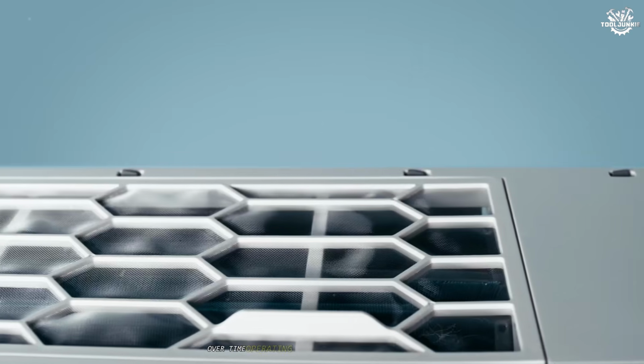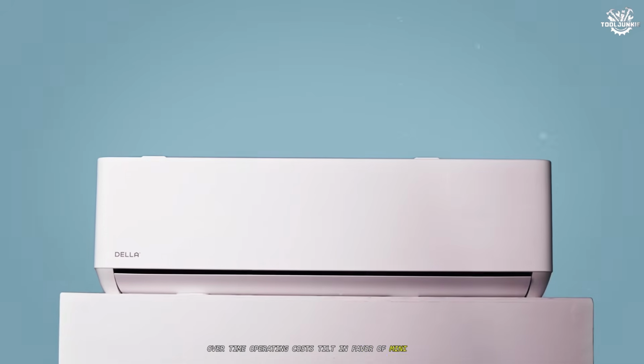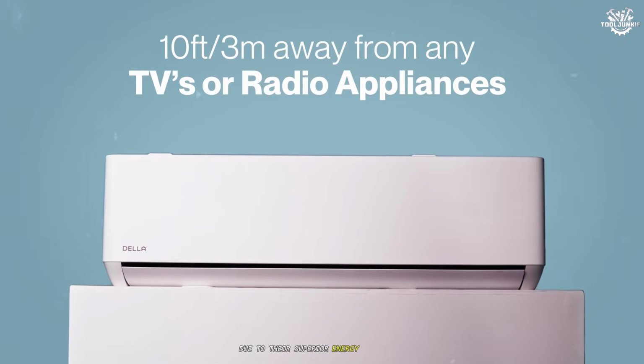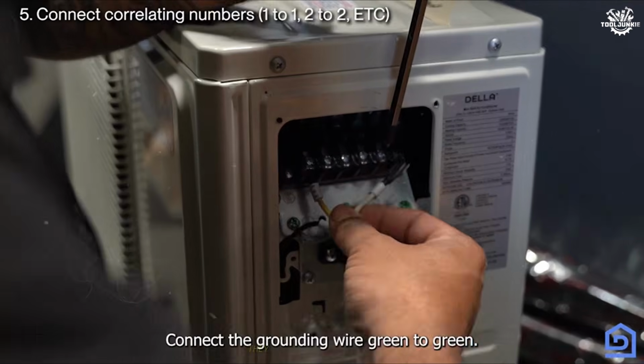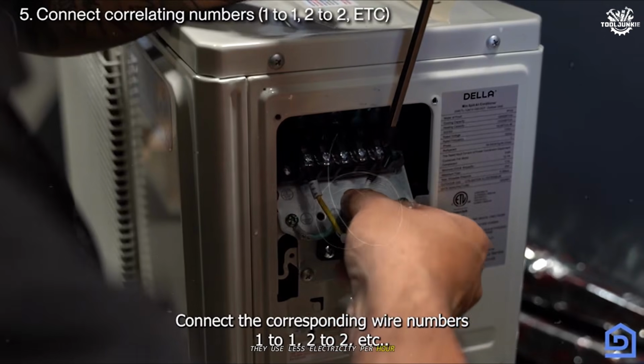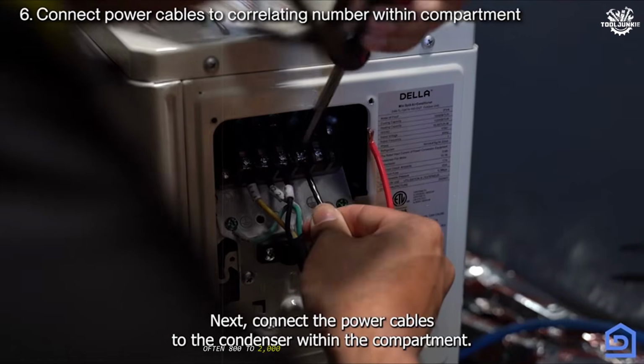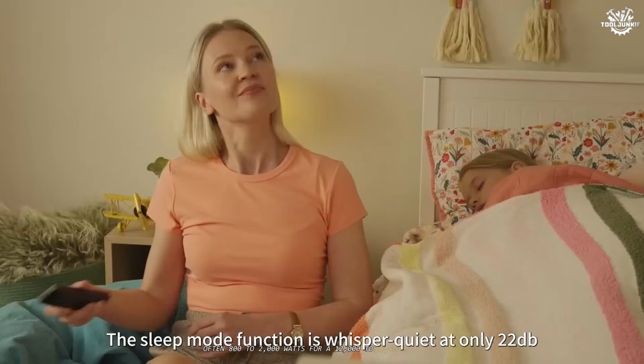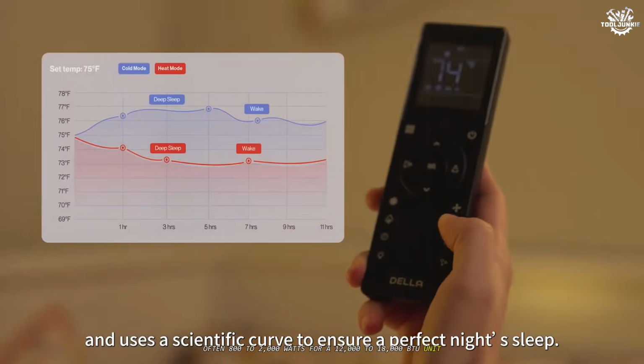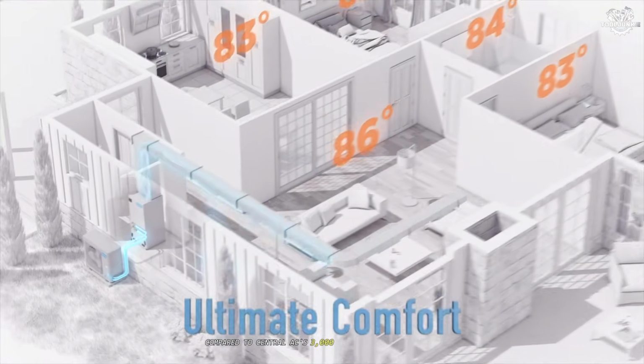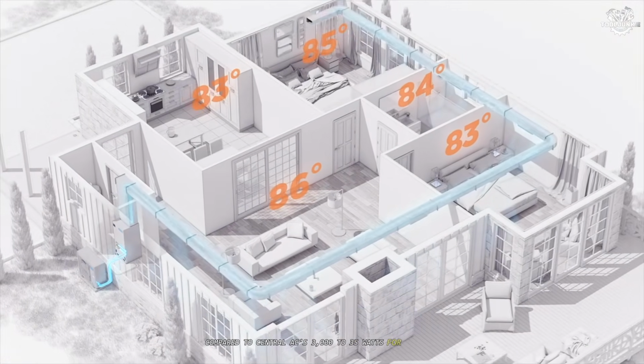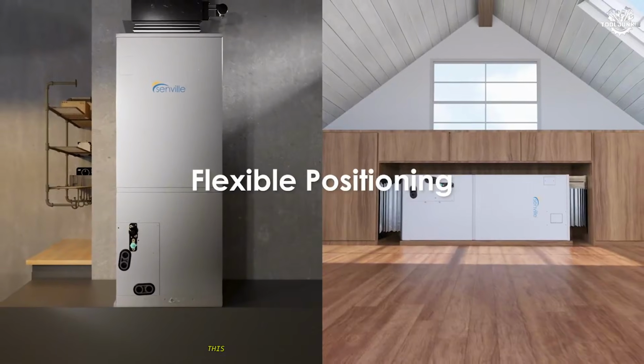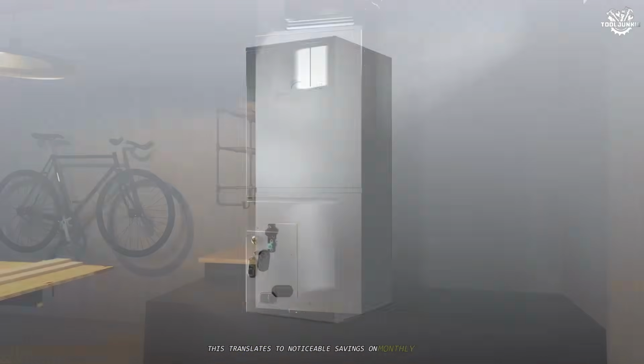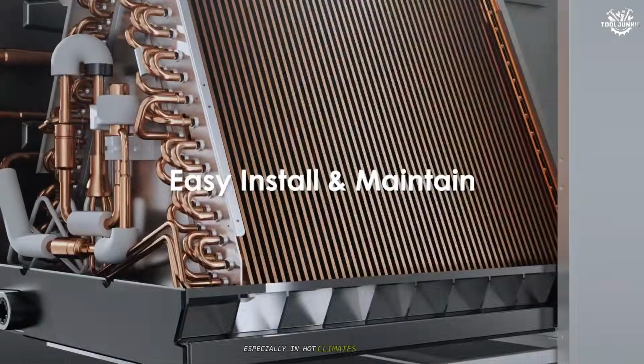Over time, operating costs tilt in favor of mini-splits due to their superior energy efficiency. They use less electricity per hour, often 800 to 2,000 watts for a 12,000 to 18,000 BTU unit, compared to central AC's 3,000 to 3,500 watts for similar capacity. This translates to noticeable savings on monthly bills, especially in hot climates.